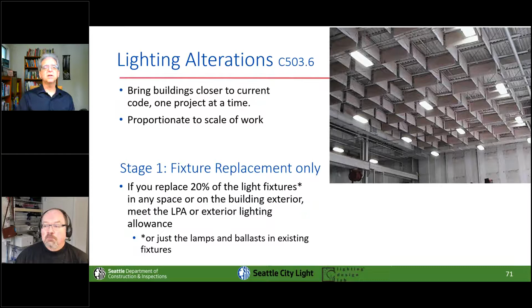For lighting alterations, we have a 3-stage approach to keep it proportionate to the scale of the job. In the first stage, if you replace more than 20% of the fixtures in a space, you have to bring the lighting power in that space down to code, which usually means replacing everything with LEDs, but your client was going to do that anyway.